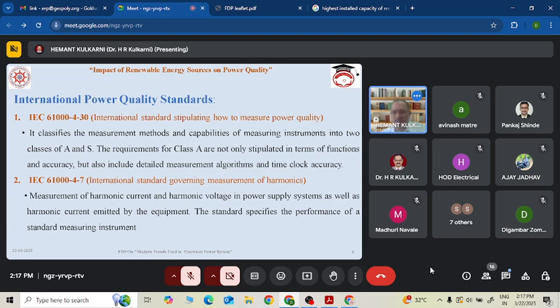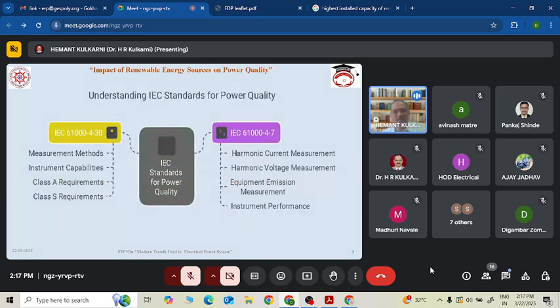I will show you here: these are the international power quality standards. IEC 61000-4-30 covers standard measurement methods, instrument capabilities, and certain classes - class A requirement and class S requirement, with some variations between them.